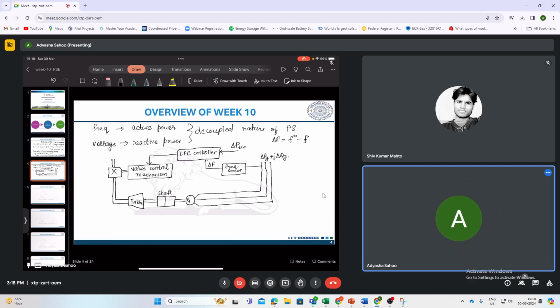active and reactive. So this part is for the active control, active power or frequency control loop. And similarly, it will have a voltage sensor for the reactive power or the voltage control loop. So similarly, here you will monitor the voltage through the voltage sensor, and that is given to your automatic voltage regulator or your AVR, and that is controlled using the field excitation of the generator. Like the frequency is controlled through the valves or gates, the voltage is controlled through the excitation or the generator field. So this is your excitation system.